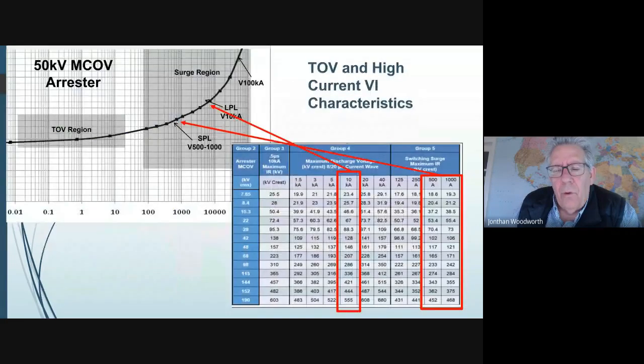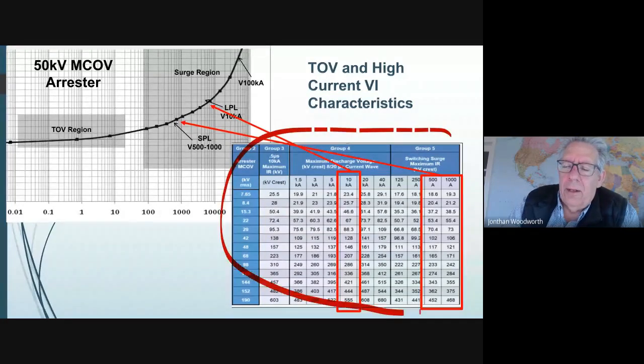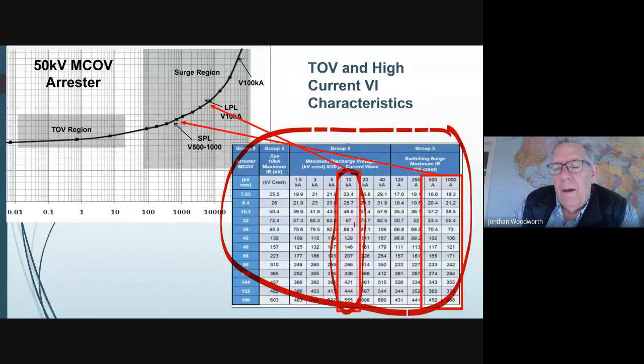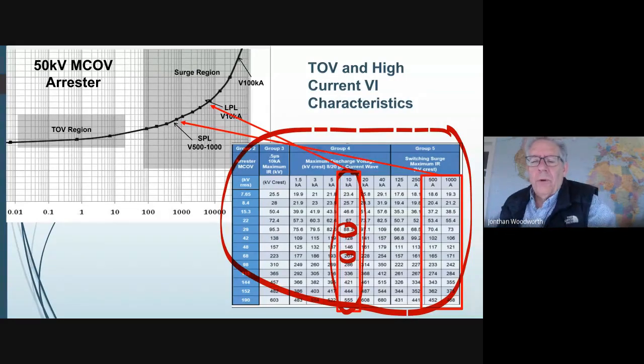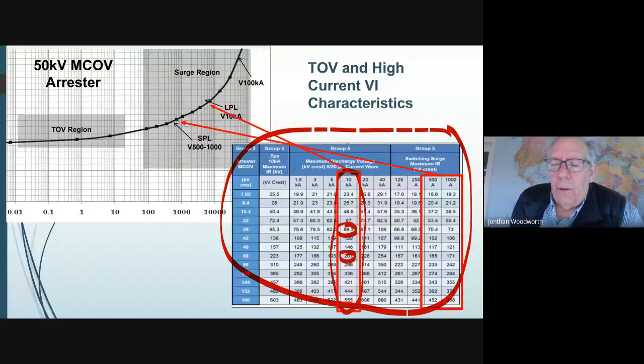Let's move on. One of the things that you'll run into if you ever start using arrestors is you'll find these tables, and they can get kind of confusing sometimes. And what this says is that at 10,000 amps, this is what the voltage will be on this arrestor. So if you are trying to determine whether to buy an arrestor from ABB versus one from Siemens versus one from Hitachi, you can then compare these numbers from the data sheets that all manufacturers supply.